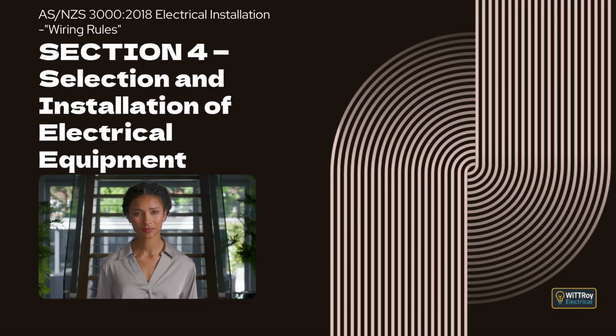Clause 4.4.3 Earthing contacts. This clause explains that every socket outlet must have an earthing contact, except where socket outlets are used for SELV or PELV systems, in which case no earthing contact is permitted. Clause 4.4.4 Switching device. This clause introduces requirements for controlling socket outlets. Clause 4.4.4.1 General. This clause explains that each socket outlet must normally be controlled by its own separate switch that meets the relevant switching standards and operates in all active conductors.